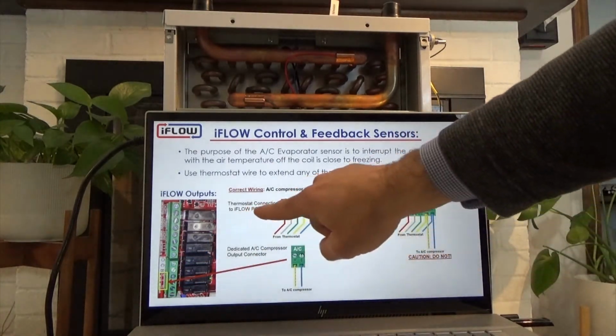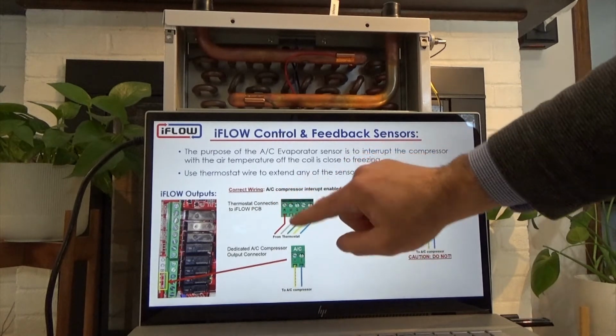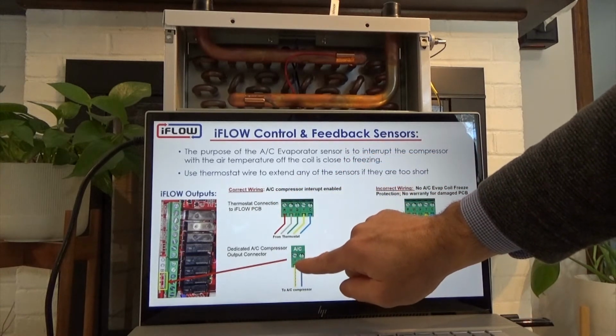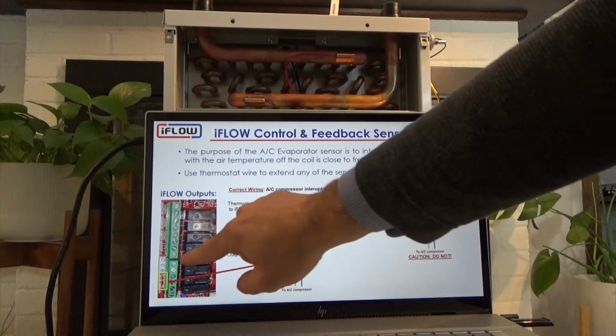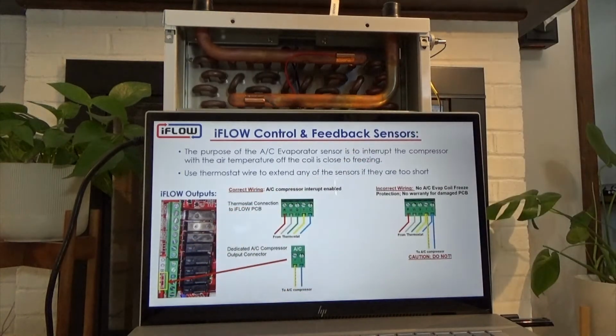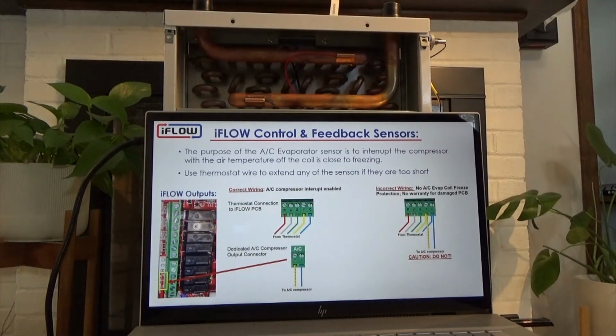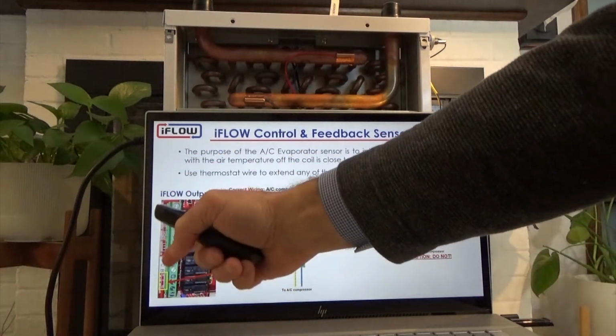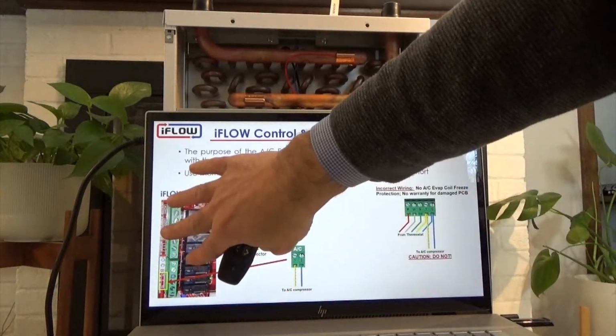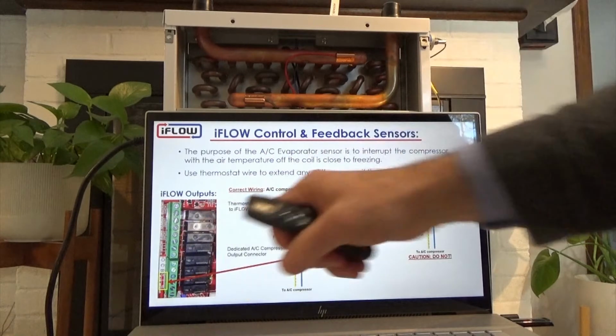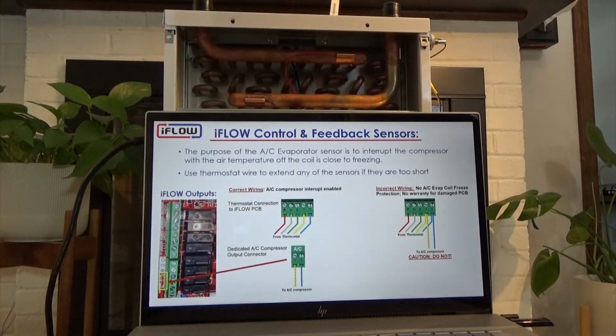So you wire your thermostat as you would normally, and then wire your AC output to the compressor from the dedicated output on the right side of the unit. It could be right side, could be left side, depends on the model. In this model that we're looking at, the 2-zone board, it's on the left side, and I'll show you in more detail where that is.